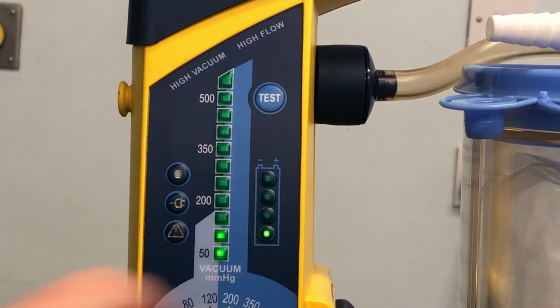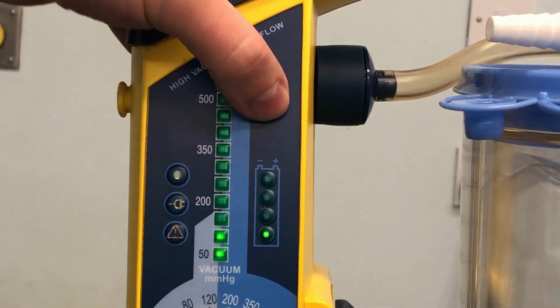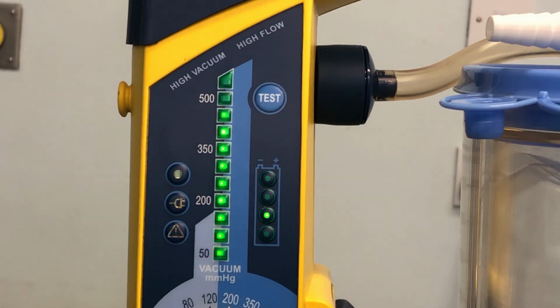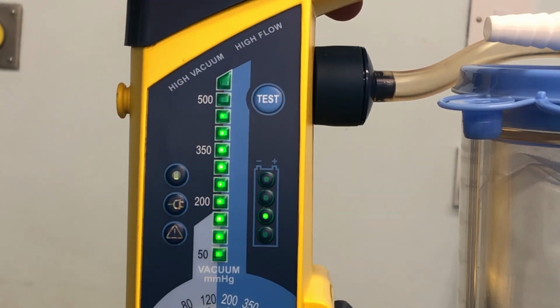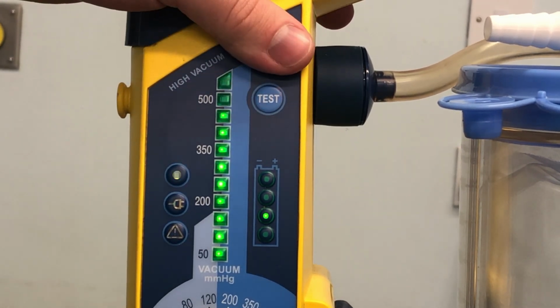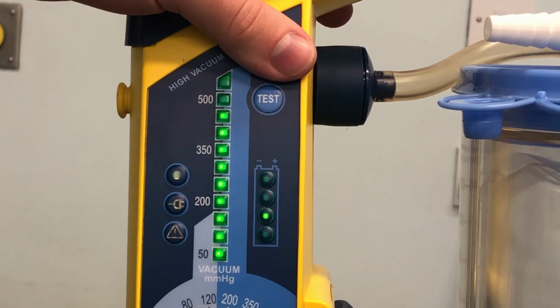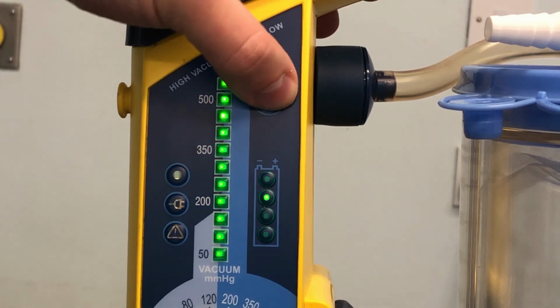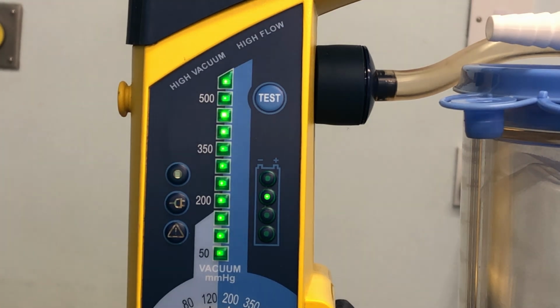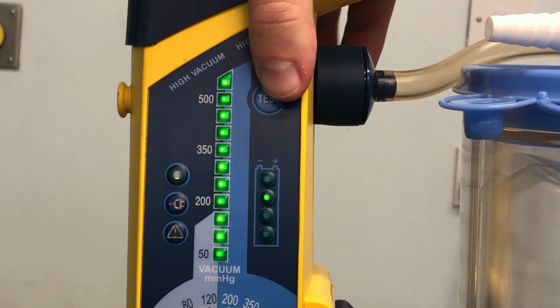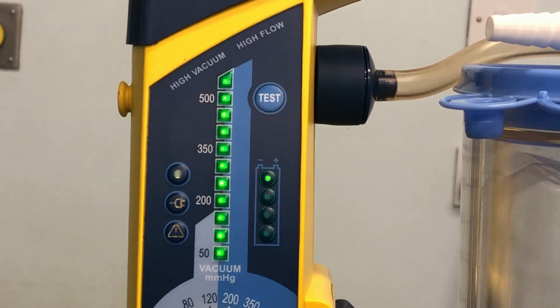Step 1 is checking for occlusions in the suction system, including the canister and tubing. Step 2 is checking the vacuum build-up efficacy of the pump system, i.e. how much vacuum is built up within 3 seconds. Step 3 is checking the max achievable vacuum level of the LSU. It reaches this level within 10 seconds. And step 4 is checking for air leakages in the pump system, including canister and tubing.